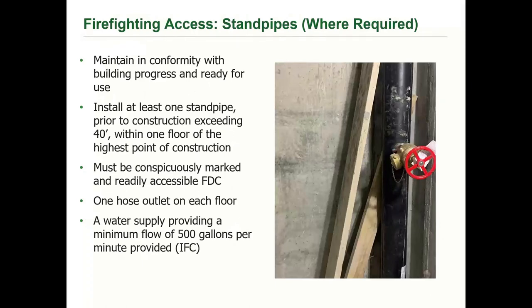Standpipes, where required, are simply the most important fire protection feature on a construction site. It's the quickest way to convey water to the upper floors of a place under construction until the sprinkler system goes online. They have to go up with the building. Once the building hits 40 feet, the FDC has to be conspicuously marked. There has to be a hose outlet on each floor. The minimum water supply must be 500 gallons a minute per the IFC.